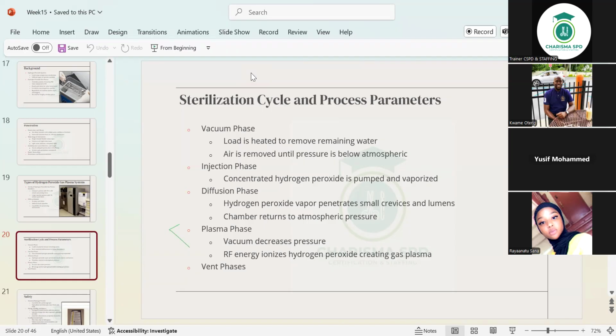Okay? So the injection phase: concentrated hydrogen peroxide is pumped and vaporized. And then the diffusion phase: hydrogen peroxide vapor penetrates small crevices, which are the hard to reach areas of the instruments and lumens. And then the chamber returns to atmospheric pressure. You see, after the exposure, after the penetration.